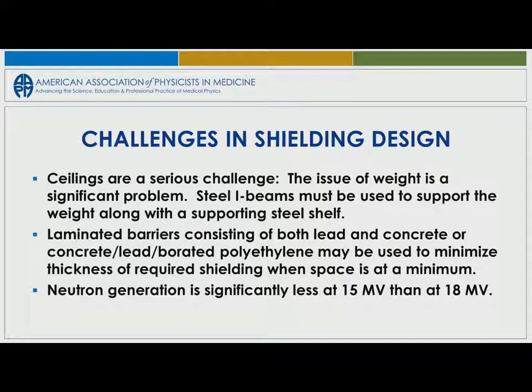The other thing you can have an influence on if you're looking at shielding calculations is, at least I've never seen that big a difference clinically between having a 15 and an 18 MV machine. But the difference in neutron production is significantly different. If you can keep them to a 15 MV unit instead of an 18, your neutron shielding is much, much simpler.